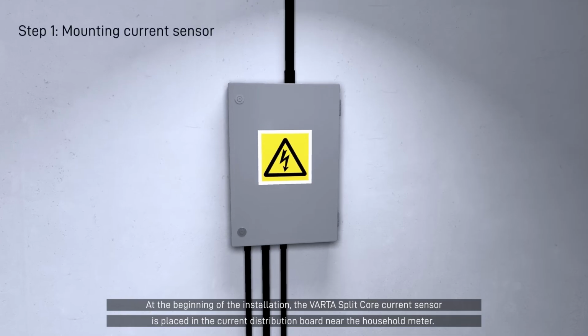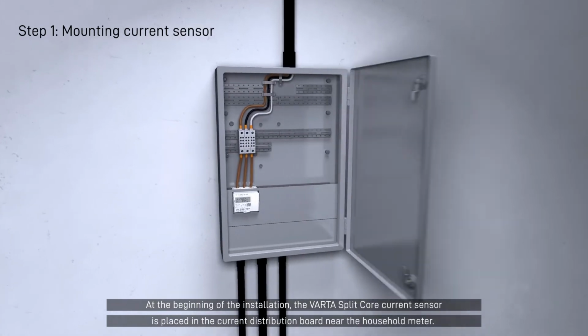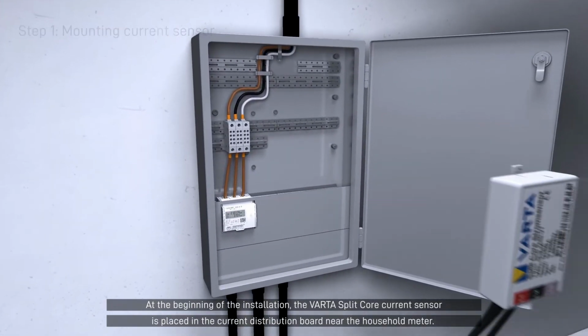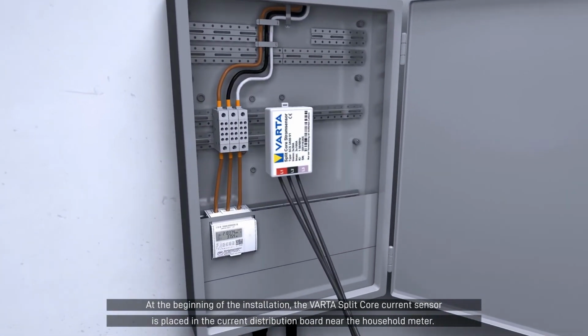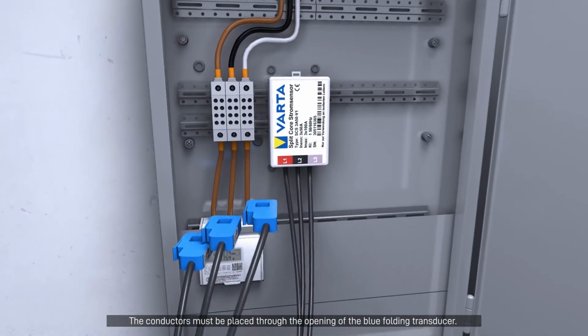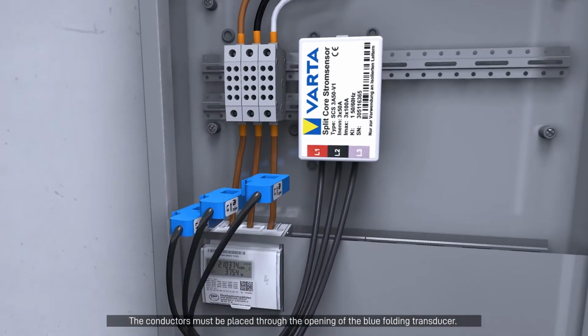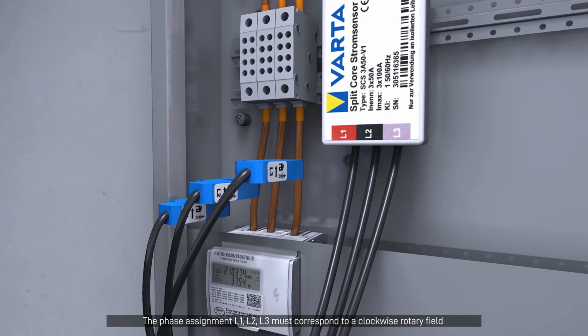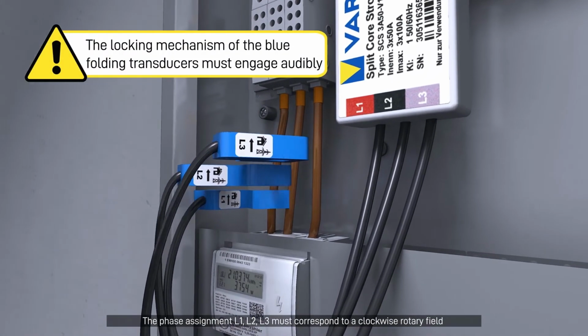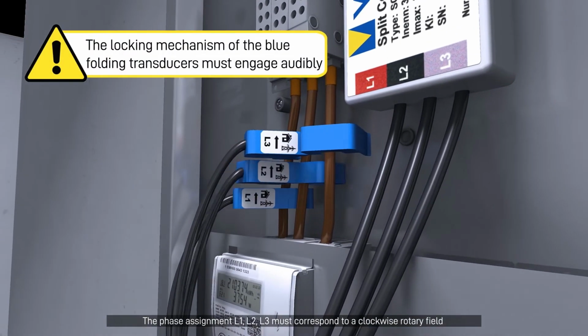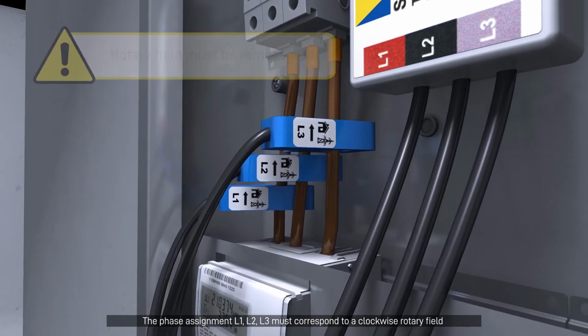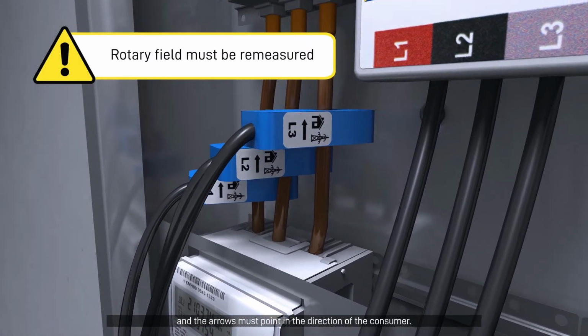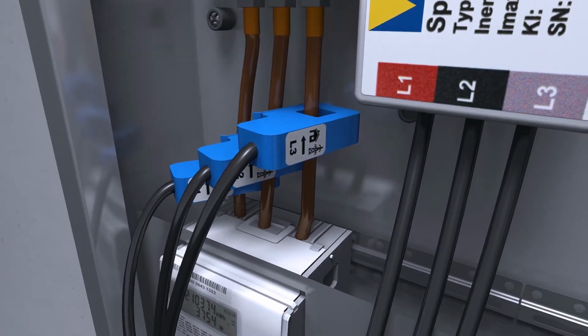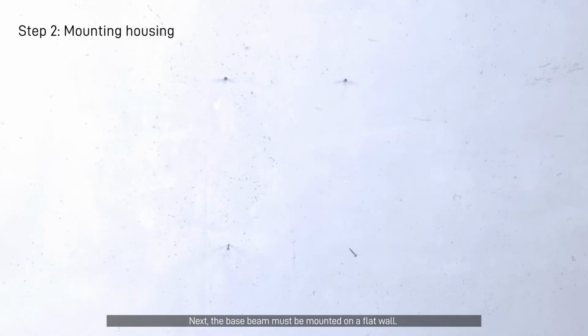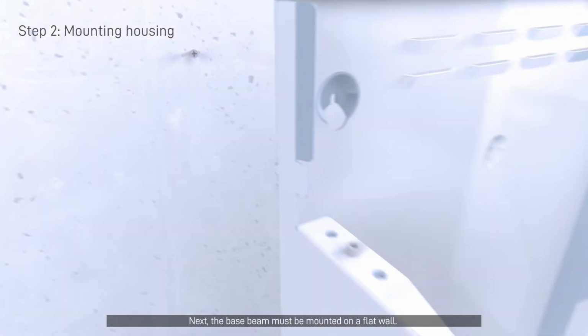At the beginning of the installation, the VARTA split core current sensor is placed in the current distribution board near the household meter. The conductors must be placed through the opening of the blue folding transducer. The phase assignment L1, L2, L3 must correspond to a clockwise rotary field, and the arrows must point in the direction of the consumer. Next, the base beam must be mounted on a flat wall.